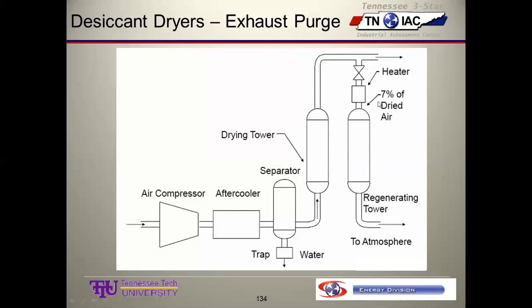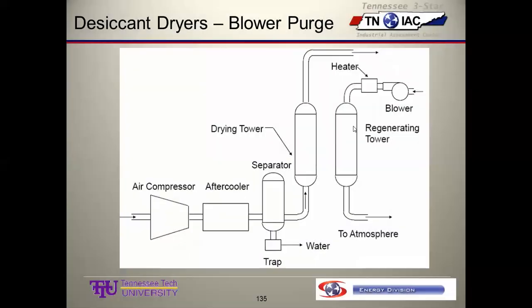We said 15% before, now we're down to 7%. So if this is a 1,000 CFM rated dryer, we're going to pull 70 CFM, heat it up to 250 or 300, and run it through this tank. And of course, this tank gets pretty hot if you've got 250, 300 degree air going through it. So it's recommended to insulate these towers on the heated dryers. Even though you don't see a whole lot of people that actually do that, it's a good recommendation, not only to save energy, but to keep personnel from burning themselves if they happen to bump into this.